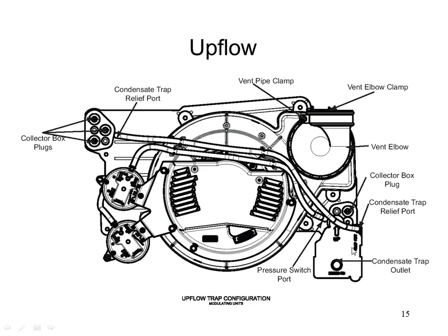The condensate trap's in the bottom right. But if I were to flip this unit upside down and use it in a downflow application, then my condensate trap, instead of being down here in the bottom right, he'd be up here on the top left. Obviously, water doesn't do a very good job of flowing uphill, so I would need to do something different.